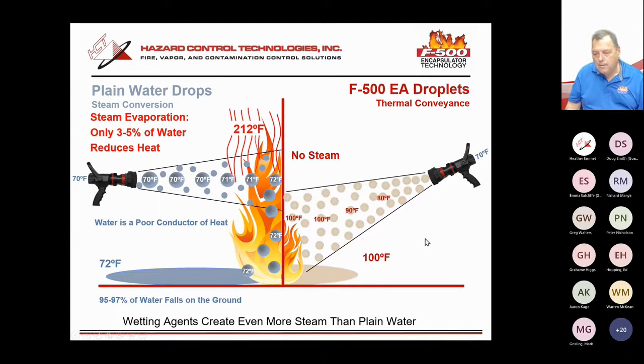And when we talk about thermal runaway and lithium-ion battery, everything I've seen and read from NFPA, UL, and FM Global says the big problem is thermal runaway and reduction of the heat - we need copious amounts of water to reduce the heat. Here's why: the water is not very effective at reducing heat compared to the F500.